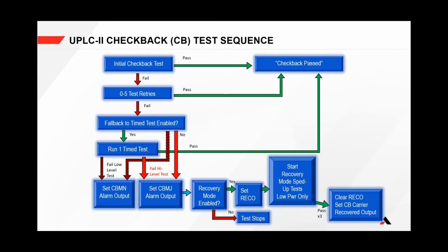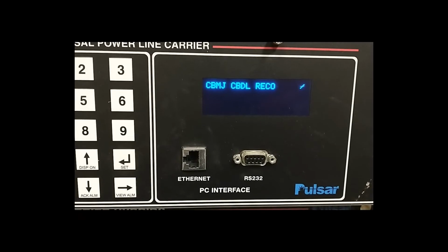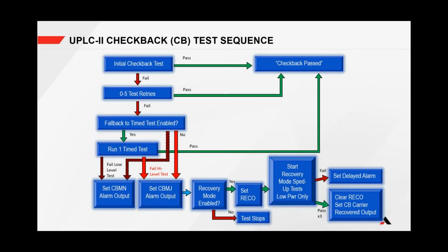If this condition is not met before the recovery window expires, then the delayed alarm will also be set, shown here on the UPLC front display. The UPLC will remain in recovery until passing 3 consecutive checkback tests.